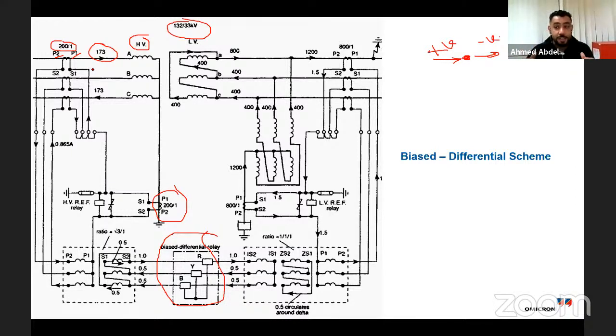The polarity of the CT: in the sinusoidal wave, the current is positive in the first half cycle and negative in the second half cycle. So if the current is flowing from P1 to P2, the secondary current will be opposite by 180 degrees. It means that if the current is flowing from P1 to P2, on the other side it will be from S2 to S1.